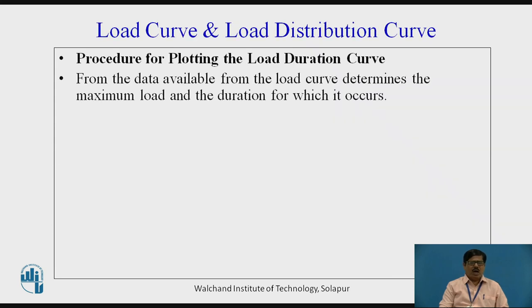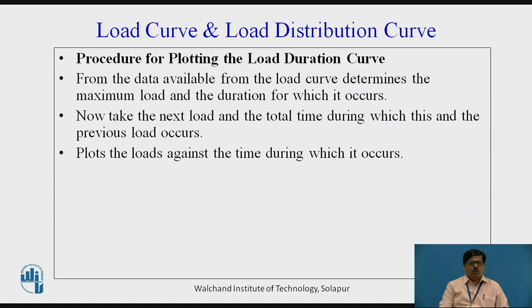Now, let us see how we plot the Load Duration Curve. From the data available from the Load Curve, we can determine the maximum load and the duration for which it is occurring. Then take the next load and the total time during which this load and the previous load occurs. Plot the loads against the time during which they are occurring in decreasing order of magnitude. The Load Duration Curve can be drawn for any duration of time — for a day, month, or year — and the whole duration is taken as 100%.